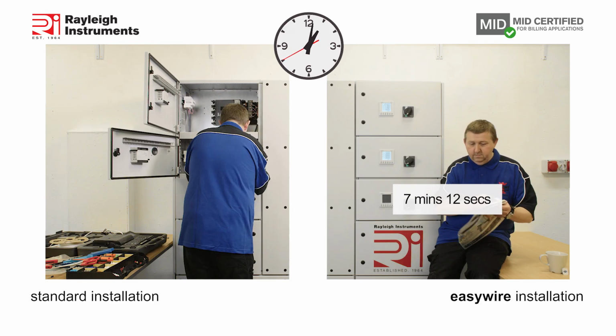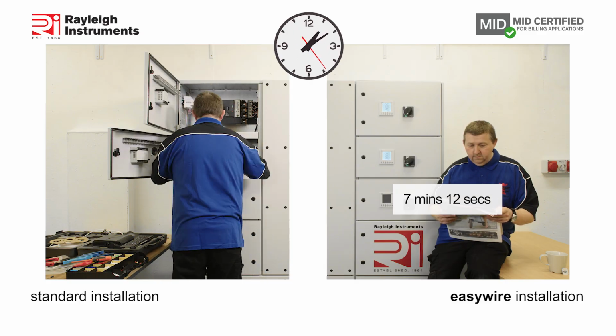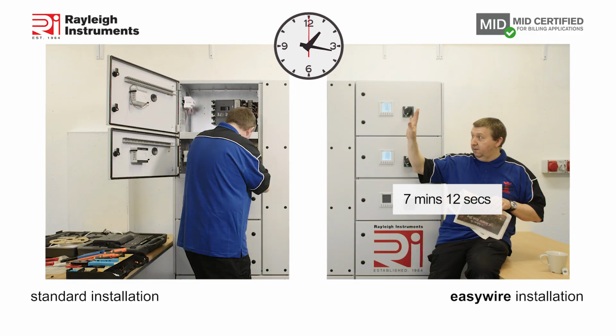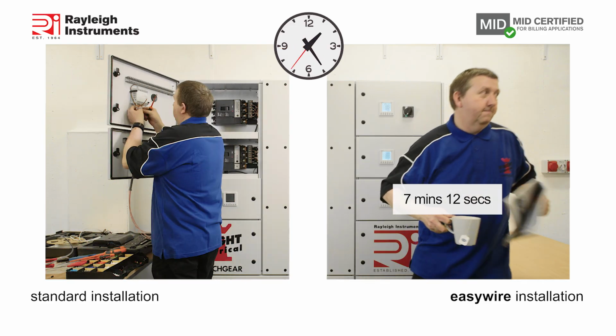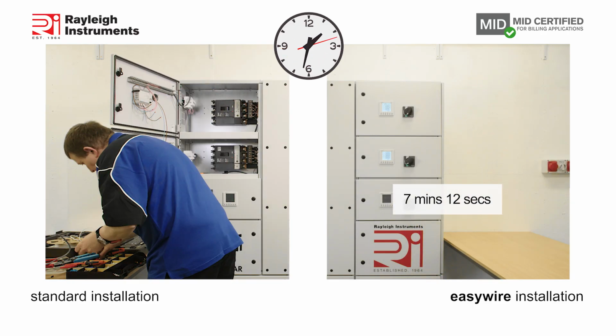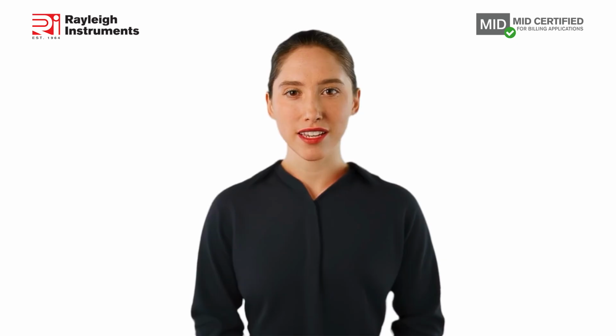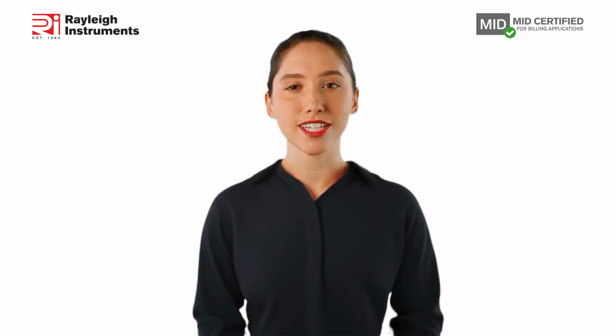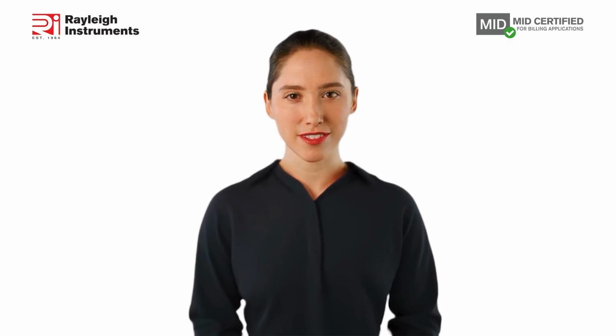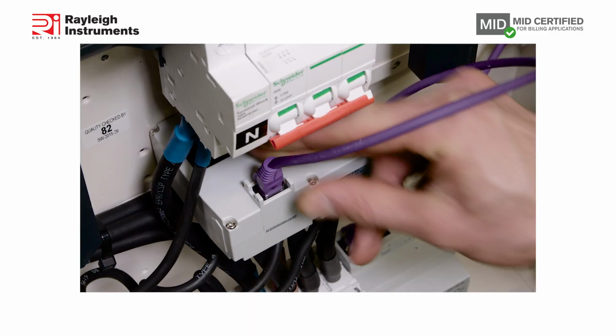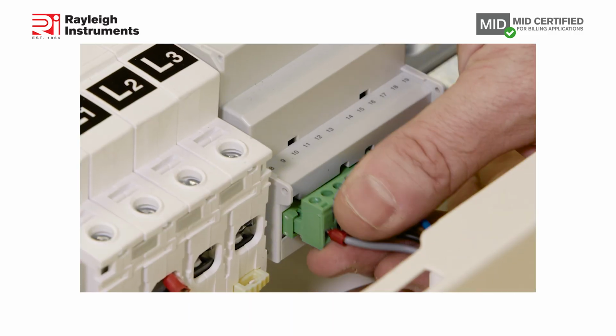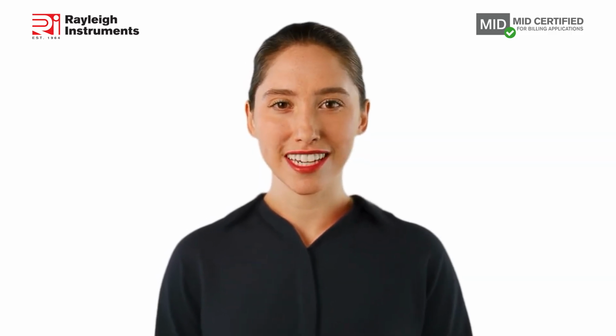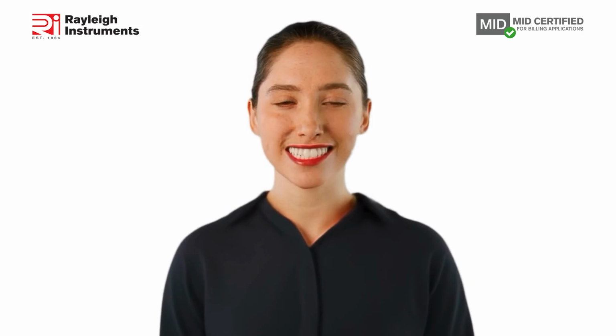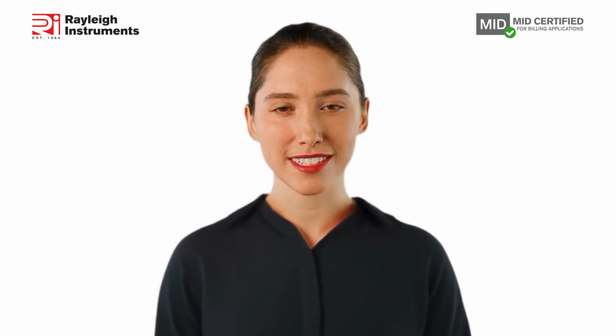Another consideration is that Easywire current transformers have integral circuitry that prevents the buildup of high voltages if they are disconnected under load. No need for current transformer shorting terminals with Easywire. The proven Easywire design has been successfully in service since we launched it in 2012. The simple plug-in connection for both the current and voltage inputs and outputs makes the installation process so much quicker with reduced testing time. Easywire products are fully EMC tested and CE certified and can be supplied with or without cables to suit your requirements.